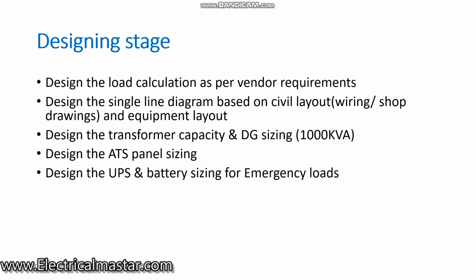And also designing the UPS and battery sizing for the emergency load. Whatever I already told, the emergency load: fire alarms, CCTV and server load. I took this load separately and did the calculation, and based on that I sized this UPS and also the battery. Even with a transformer failure, the UPS can withstand the full emergency load for 1 hour capacity. Like that, I designed it in my last year project.